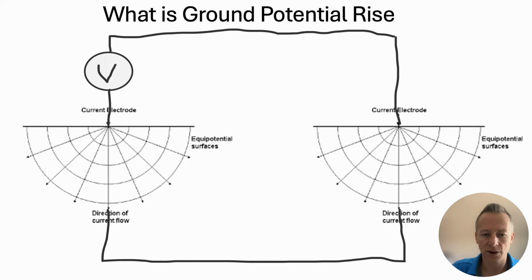So take a look at this circuit. If we take two of these dirt injection zones, and we apply a voltage source to it where current will flow, the current will go into the earth over here on this side. It will disperse into the earth, and it'll reach a point out here what the grounding people call remote earth. And remote earth is when the current is so dispersed into the earth that no more shells matter anymore. So at some point, no more of these shells matter anymore, and the current is fully dispersed, and then it's just connected to the earth.